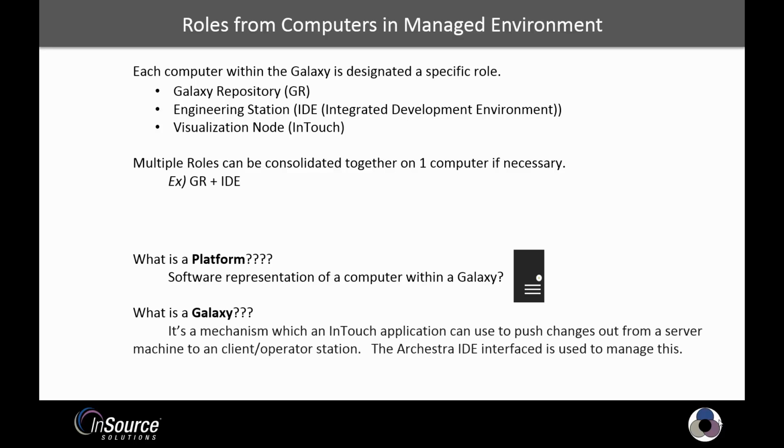Now, what is a Galaxy? The Galaxy is going to be our application. Now, it is a database, so it does require a database server to be installed. Thankfully, the installation process does this for us without us ever having to interact with the SQL Server installation. So it will be the mechanism that we will use to push out modifications from an InTouch application from a Galaxy repository, a single computer where our configuration is kept, out to client operator stations. We call that the visualization node.